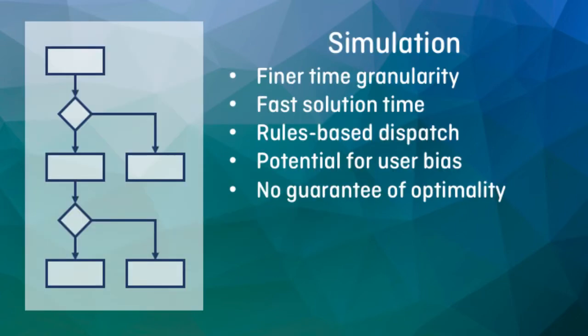Simulation can be very useful, as it often allows for a more detailed examination of operation conditions, for instance by modeling all 8,760 hours in a year. For dispatch of DER technologies, however, simulation typically relies on rules-based strategies. When certain conditions are met, different DERs might be dispatched to respond in a scripted manner. Rules-based control strategies can vary in complexity, but in practice, they are often influenced by the past experience or preconceptions of the modeler. As a result, the simulation approach does not guarantee an optimal solution.